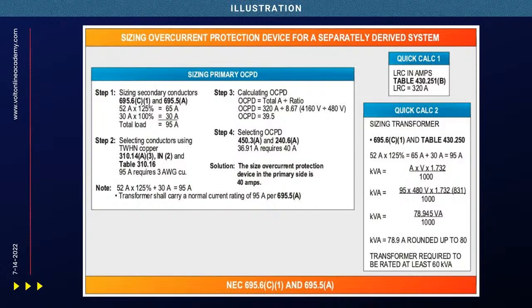Yeah. But when you look at this, and I didn't see this online or anybody showing this, but you'll take the locked rotor current, which is over in table 430.251B, and it's going to tell you that locked rotor current was 320 amps. And then I showed where you took the 4160 volt, divided by 480. That was your ratio of the transformer, which was 8.67. Divide that into 320 amps, and that's going to give you 39.5 amps. And then the next size above that is 40 amps. So on that primary side, I would at least have to have a 40 amp overcurrent device to hold that indefinitely based on that locked rotor current.